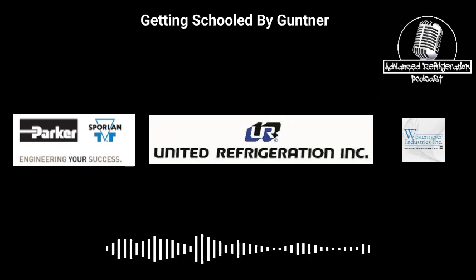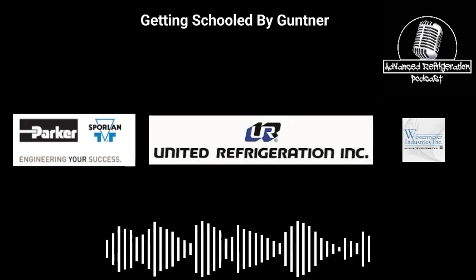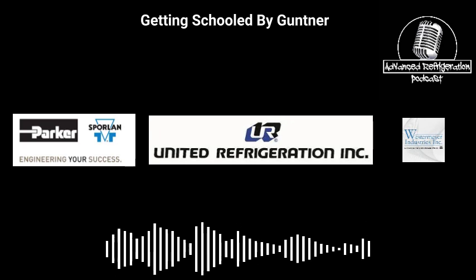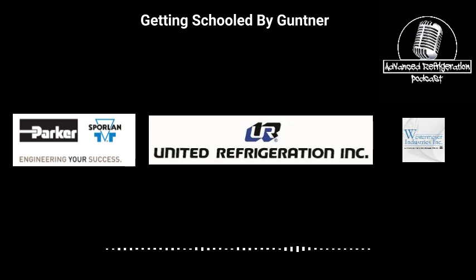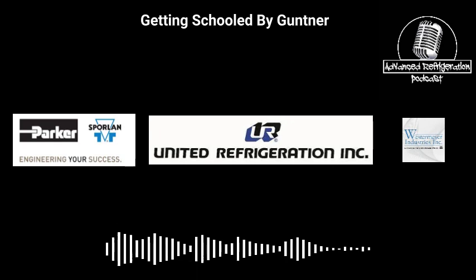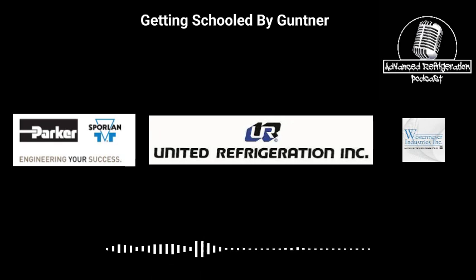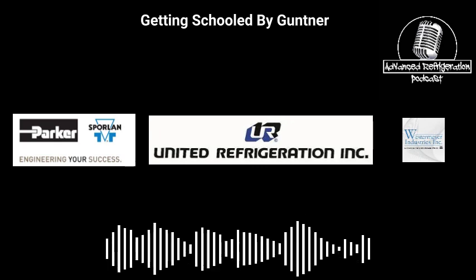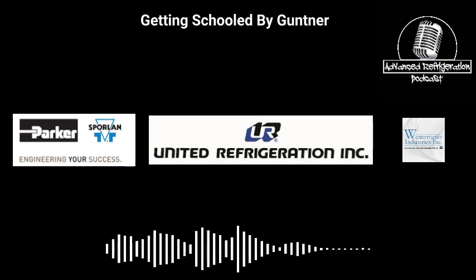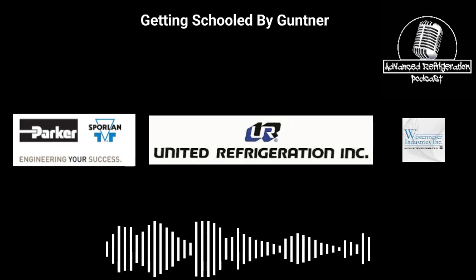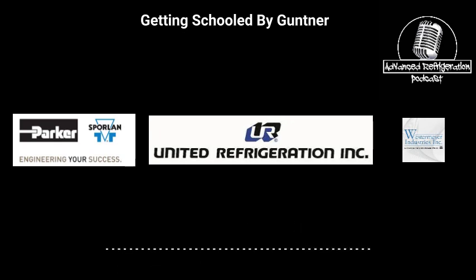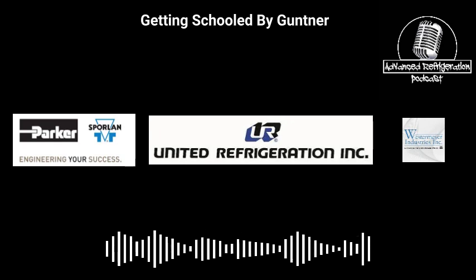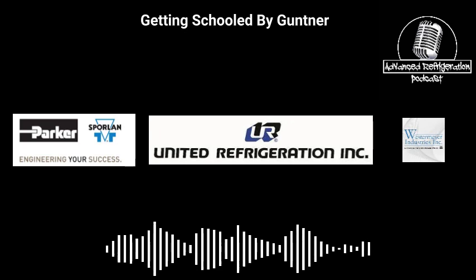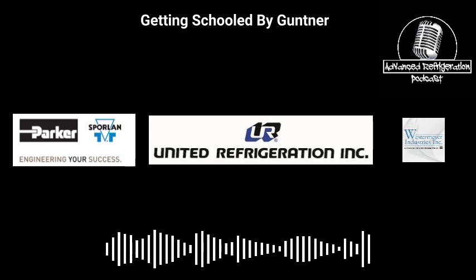Okay. So another feature that we have, these are standard features on our controller, is the bypass mode, maintenance run, and ice break mode. So for the bypass mode, we run individual Modbus lines from each fan directly to the controller. What that allows us to do is, if one of the lines of communication gets severed to a fan, then the fan will go into bypass and spin at 100%. It'll also let us know which fan is doing that. If a critical sensor or the controller fails, all fans will ramp up to 100%.